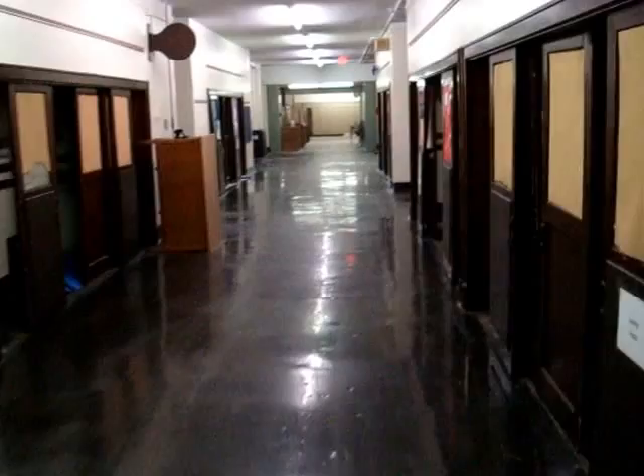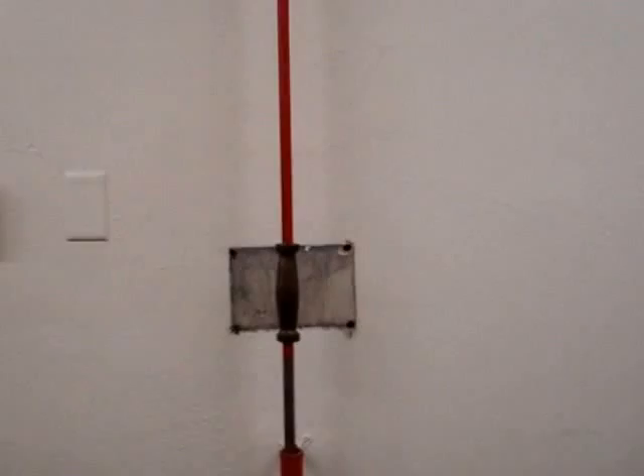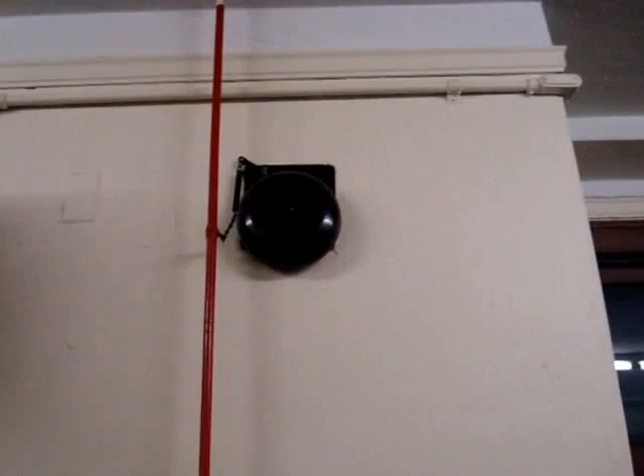But this school also has a pull rod system, which would have been originally installed when the school was first built, before the electric autocall fire alarm system was put in. All they would have had back when this building was first built would have been this pull rod, which was tied to a manual trip bell. So when you pull the rod down, it would ring this manual trip bell.